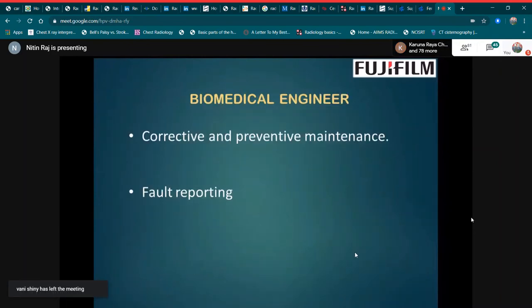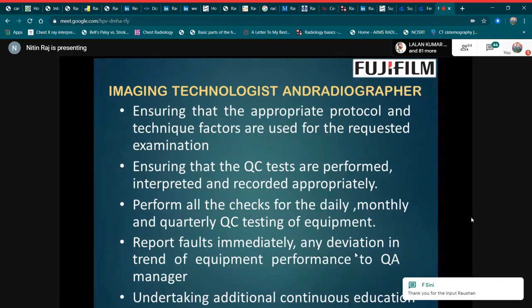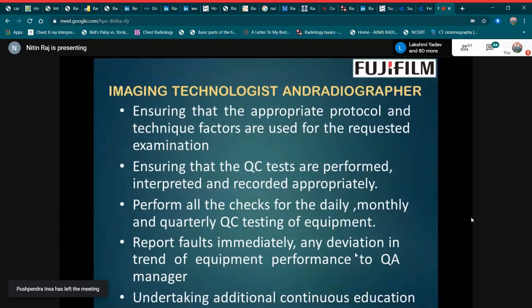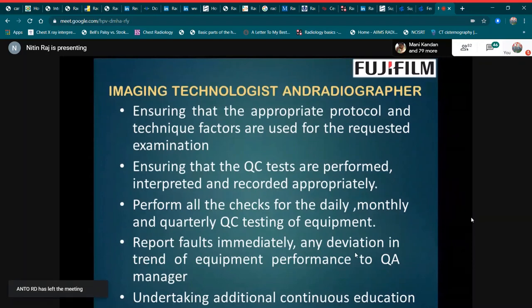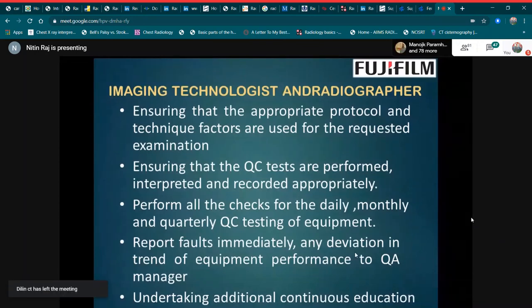The role of the biomedical engineer is corrective and preventive maintenance and fault reporting. The role of the imaging technologist includes ensuring that appropriate protocols and technique factors are used for requested examinations, ensuring that QC tests are performed, interpreted, and recorded appropriately, performing all daily, monthly, and quarterly QC testing of equipment, reporting faults immediately, and reporting deviations in equipment performance trends to the QA manager, as well as undertaking additional continuing education courses.